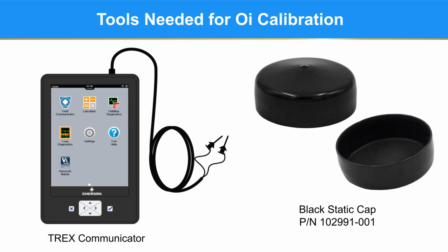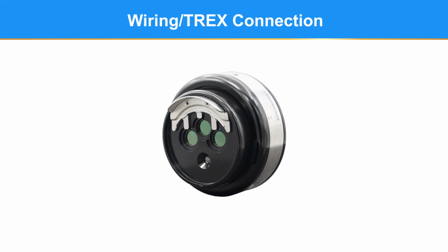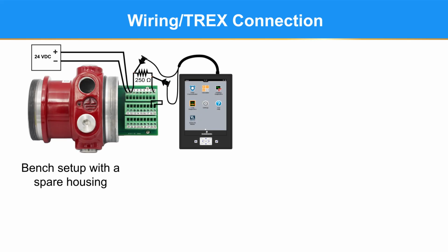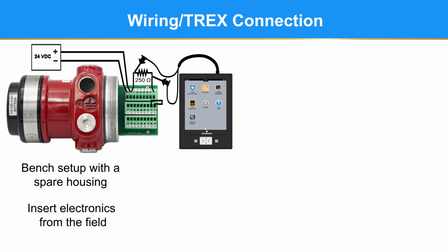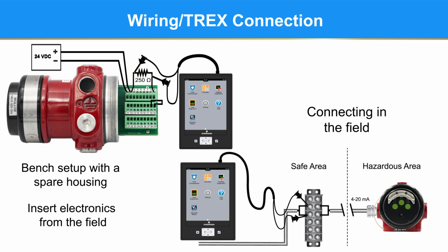The optical integrity system is all located in the electronics module, so this procedure can be done in the shop or in the field. To do it in the shop with a TREX communicator, you will have to have a spare housing. Insert the electronics module from the field into the housing, power it up, and connect the TREX across the 250 ohm load resistor. The OI calibration can be done in the field by connecting the TREX across the 4 to 20 milliamp signal, typically in a non-hazardous or safe area.